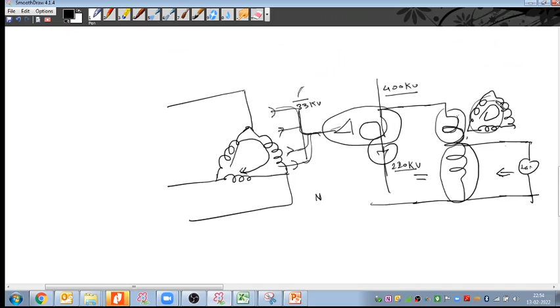So if this tertiary winding is not there, is this transformer going to consume more losses? Yes, flux will be higher because there is no opposing flux on this, which means the losses will be high. Losses are based on the flux, that will be higher. So in order to balance the flux, we need to provide the winding.